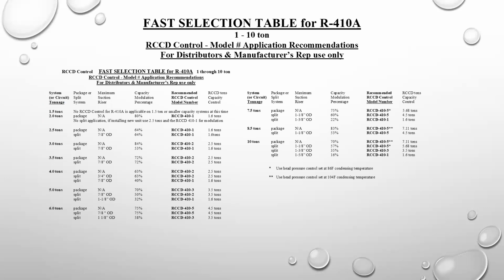It's pretty easy to design and select the system, but on this particular chart, I want you to notice that over on the left-hand side, it says system or circuit tonnage. That means if you've got more than one circuit, you can work with it. There are so many variable and flexible applications of this control, it's not even funny. That's why this is just a high level. But what I'm showing you is that you can give yourself a lot of capacity control. 10 tons is not the limit on it.